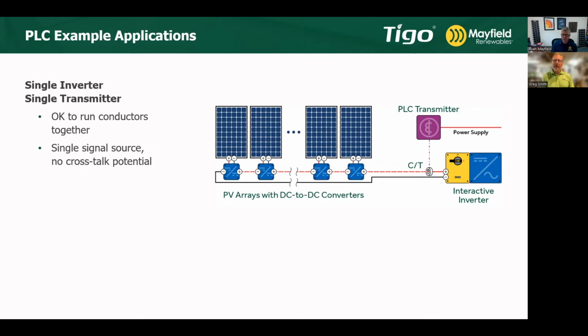Is that right, Greg? Right. So you can put 10 conductors through that CT, which is going to equate to 10 strings. So you can actually have a relatively large array on a decent size inverter supplied from a single transmitter. It's okay to run all those conductors together because you have a single source. Even if you had 10 conductors running through that CT, they're all getting the same signal. There's no crosstalk to be had because there's only a single signal going out. So run them all together in the same conduit or cable tray, whatever you want to do - it'll be fine because there's no source of crosstalk there.